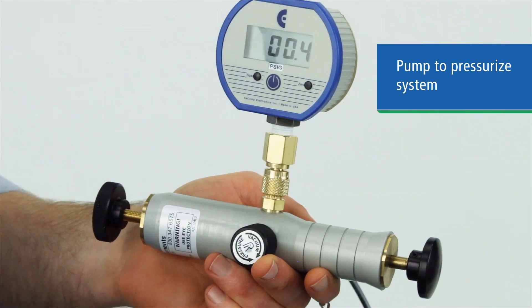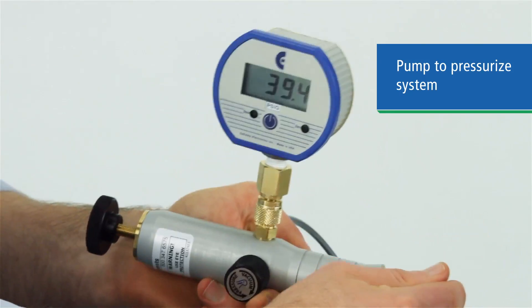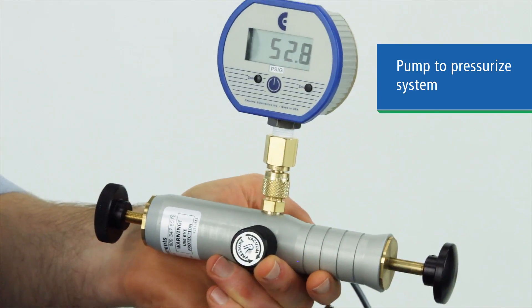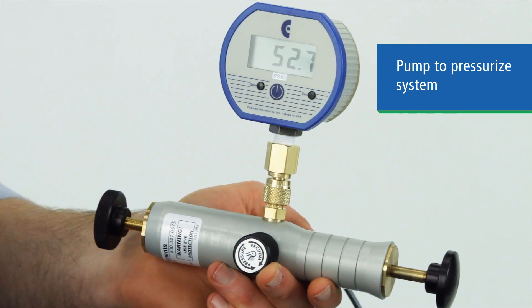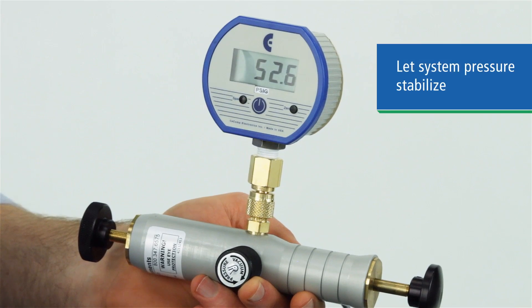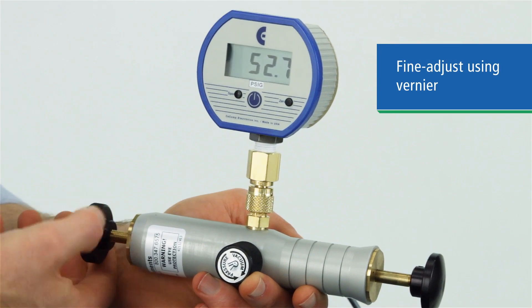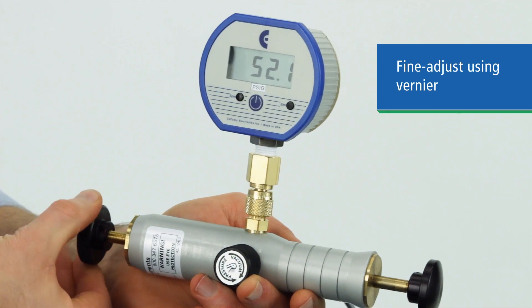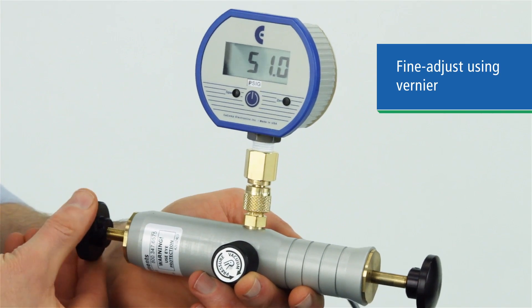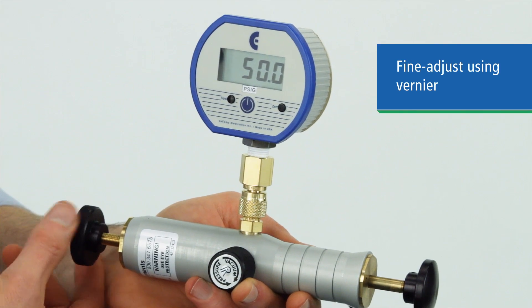Apply pressure by pumping until you are close to the value of your test point pressure. Positive pressure is created on the push stroke and negative pressure or vacuum is created on the pull stroke. Let the system stabilize for a minute as the air temperature may change as pressure or vacuum is applied. Then use the vernier adjustment to change the pressure incrementally.